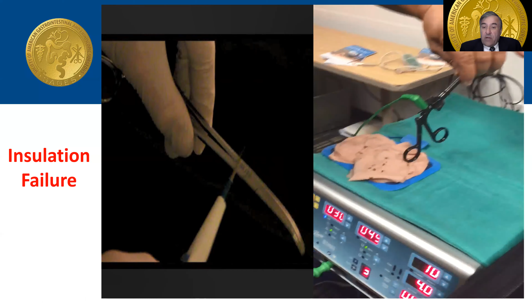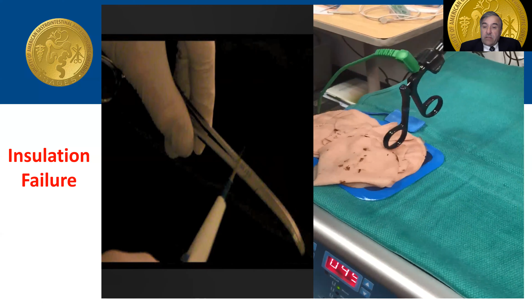You rerun the whole thing. This is an instrument that was freshly unwrapped for a demonstration, and then the holder was burned, and then we demonstrated that there is an insulation burn. Up to 30% of these instruments can have insulation failure right out of the wrapper.